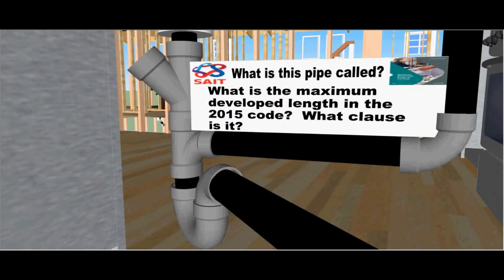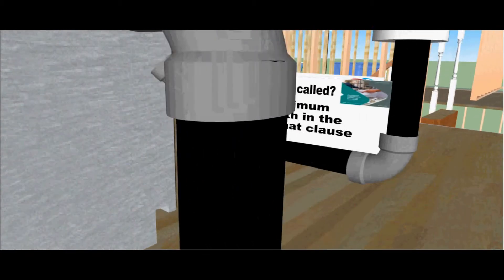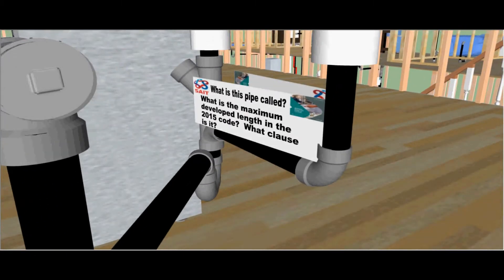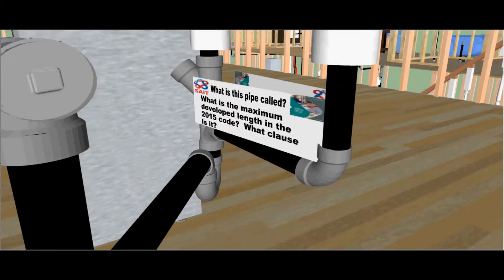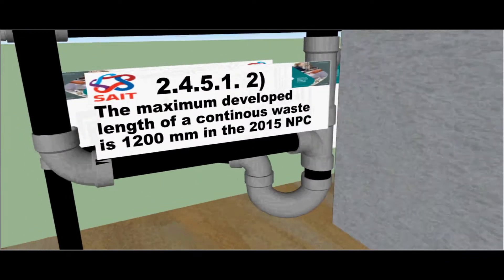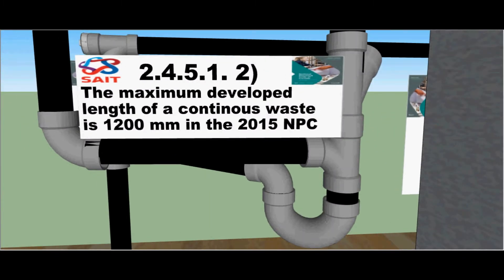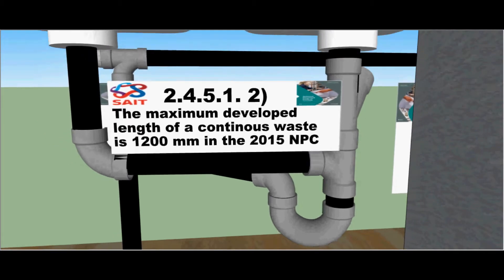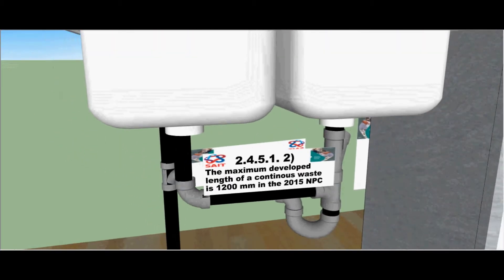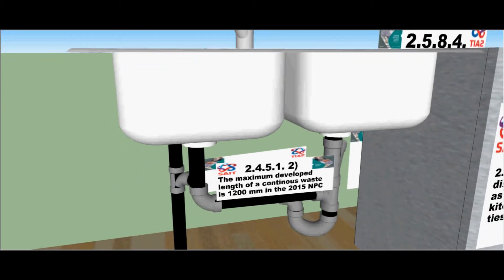What is this pipe called? What is the maximum developed length in the 2015 code? What clause is it? The maximum developed length of a continuous waste is 1200 millimeters in the 15 code. You can find it in clause 2451 subsection 2.